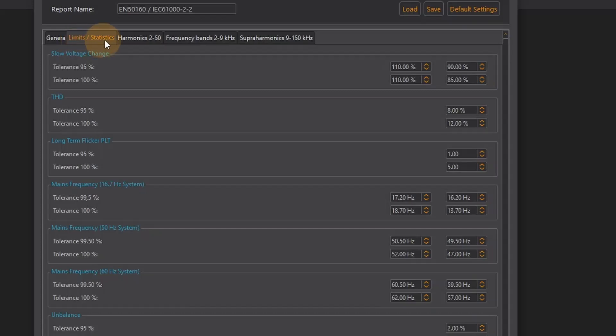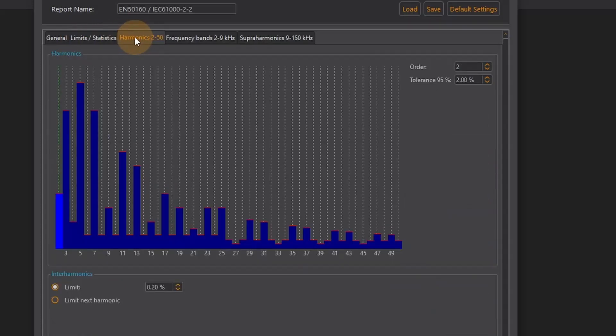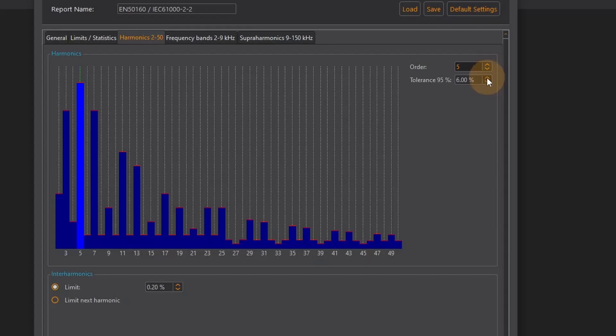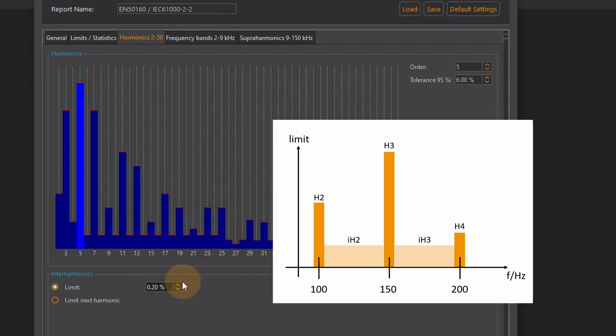The limit values of each individual voltage harmonic can be edited in the harmonics 2-50 tab. To select the order of a harmonic voltage I simply click on a column in the diagram or I use the order field at the top right. I can adjust the tolerance level below. For the interharmonics I can enter a fixed limit value or accept the limit value of the next harmonic.